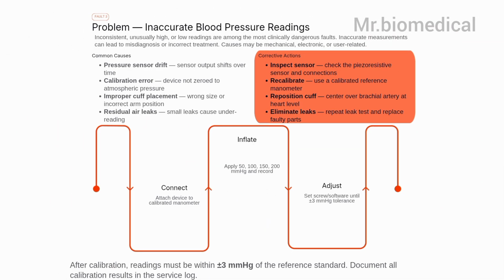Then inaccurate BP readings. Now we are going to discuss the most dangerous fault. The monitor is working, the cuff is also inflating. You might think, yeah, the BP apparatus is working correctly. No, but the readings are wrong. Why is this dangerous? Because doctors make treatment decisions based on this value. If a patient has a higher BP or lower BP, they only know by this equipment. This can lead to unnecessary medication, or some patients may not receive medication on time. So what causes inaccurate readings? A drift in a sensor or calibration errors, again air leak, wrong cuff placement. The cuff should be placed properly, and incorrect cuff size.